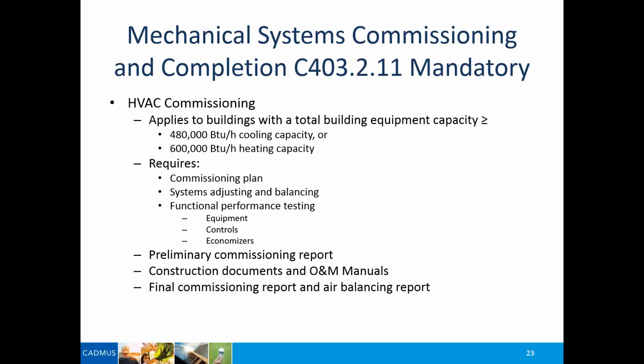So again, the Building Commissioning Association is very much behind this. We've tried to tweak the code this last time to actually put some teeth into who is supposed to be doing commissioning. Right now, the code requires a registered design professional to do the commissioning, and that has different meanings in different states. But the registered design professional right now is qualified to do commissioning underneath the provisions of this code. So you don't have to be SMACNA certified or BCA certified, or I know there's other commissioning organizations out there, but there's no criteria that way. It just says registered design professional. Okay, so that's kind of completing the whole package on the mechanical side right now.